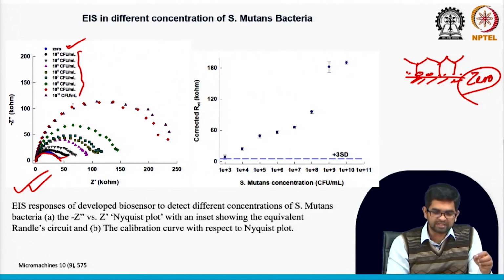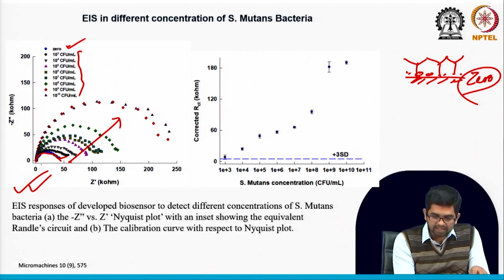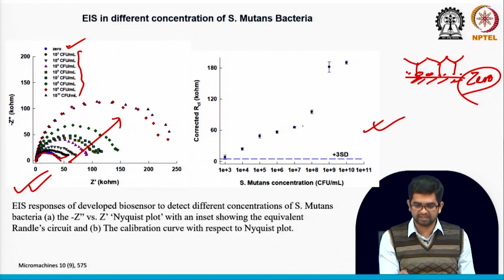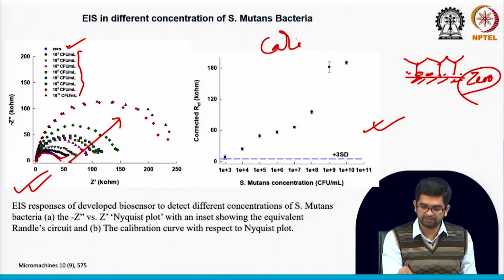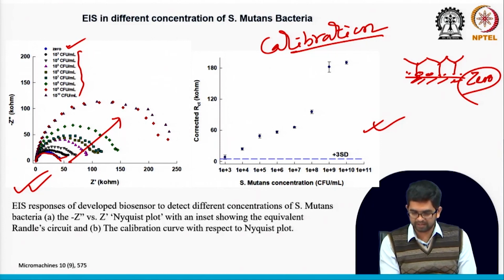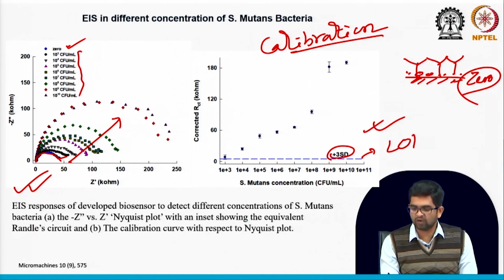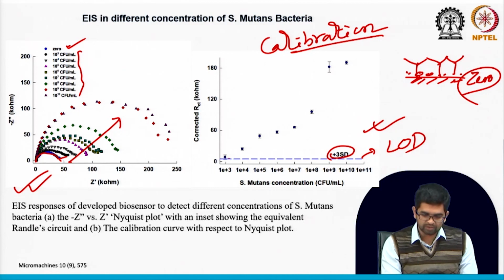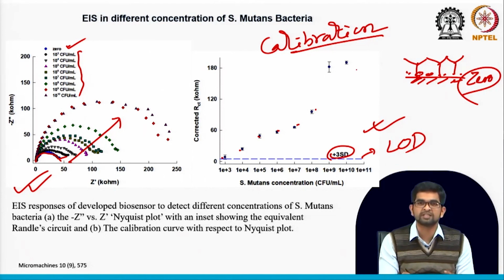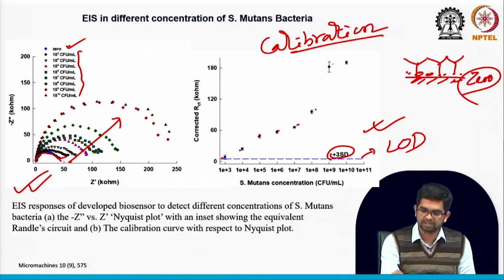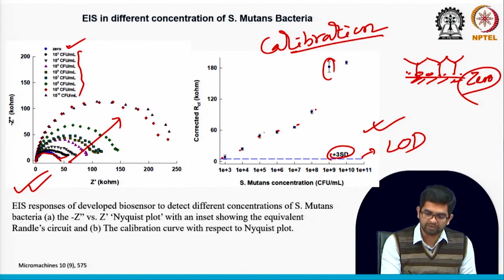Now we are increasing the concentrations. See, the RCT value increases, and this RCT value we are putting on the left hand side. This is the calibration curve. I already told you how to get the 3 times standard deviation of the 0, and this is 3SD, and based on this we can determine the LOD, limit of detection, right? You can see, we measure each concentration 3 times. 1, 2, 3, 4, 5, 6, 7, 8, 8 different concentrations we measure, and the error bar means this much standard deviation we are getting for each concentration, right? And we measure all the RCT values and we plot them.